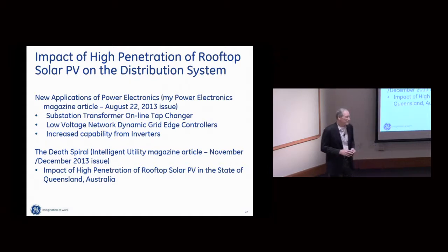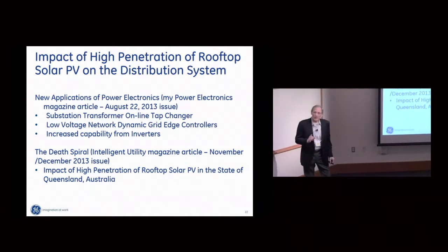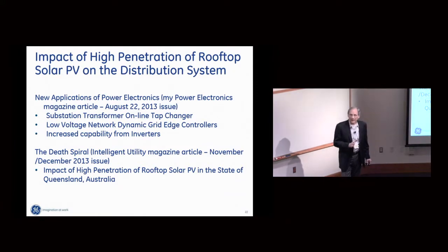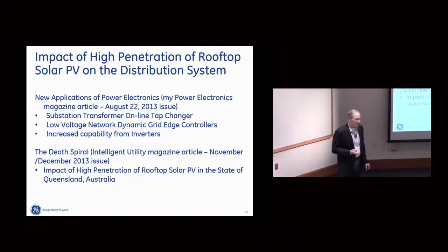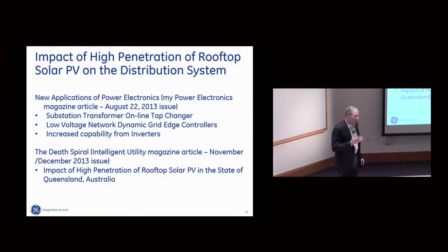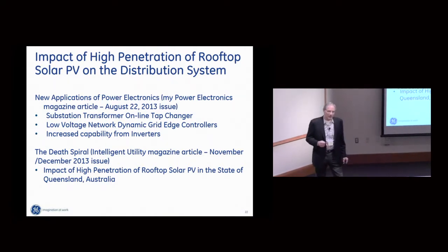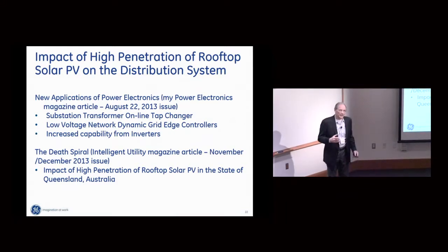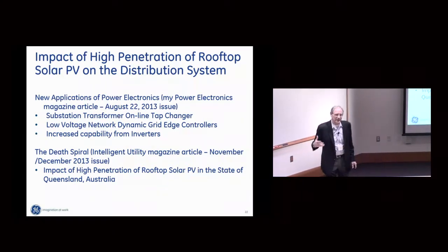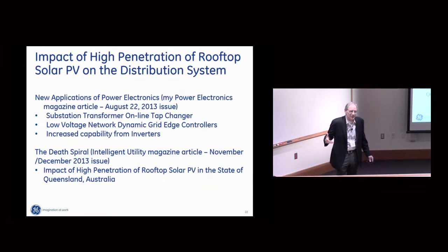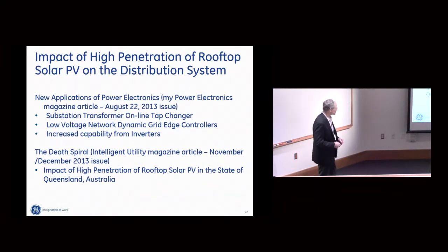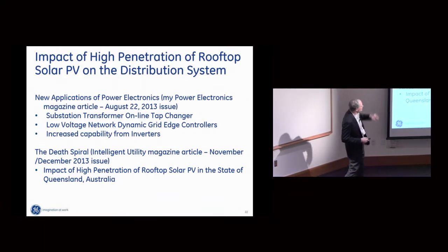Now with 35% penetration, it was operating 90 to 100 times per day, with a lifetime of 2 years or less. So I'm thinking, wow, we need to rethink the future grid — any kind of penetration of renewables could be much more volatile. Think about control: how do we control the future grid? Mechanical means are just going to wear out, it's not feasible. That's why I wrote this article for Power Electronics magazine.